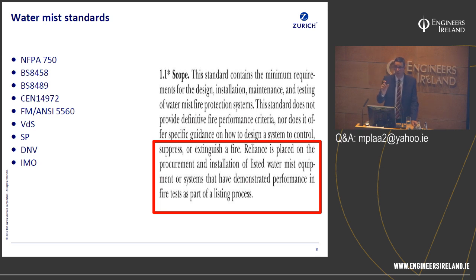So there's two important parts there, and often in the projects I see, they may have only done one element. They might have done the fire testing, but they might not have also done the listing and testing of the components. So some of the better manufacturers will actually have done both parts. So if you're going to accept a system, you want the representative fire test data for the fire test, and also you want the representative data in component testing and listing and certification. So it's like a marriage of two people. You've got to have both elements, and be careful because sometimes you'll only get just the one.